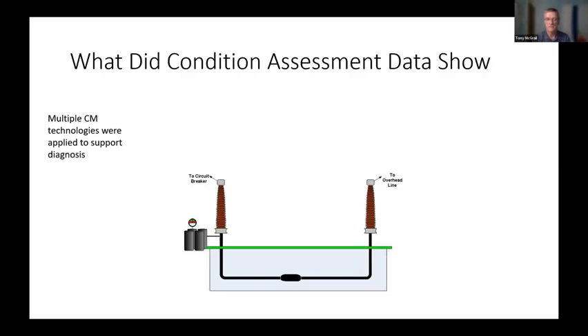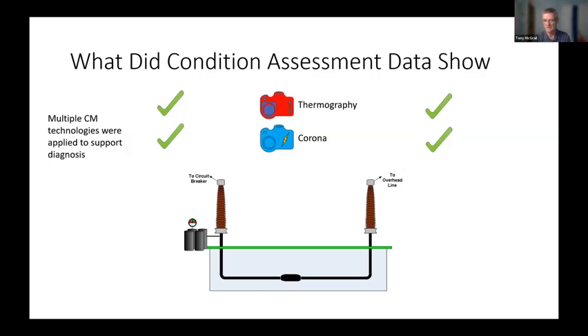And when that alert comes in, we would then apply technology in a variety of different ways to try and learn a little bit more about what's going on. We can't necessarily test the cables themselves right down in the ground, but we can go to each end of the cable, and that's where we found most of the failures were likely to occur. So first one, please, Jay. We do a thermography on either end with the cable live, no indications of any problems. Next one, please. We do a corona cam, see if we get any arcing or sparking above ground. Nothing there. Next one, please.